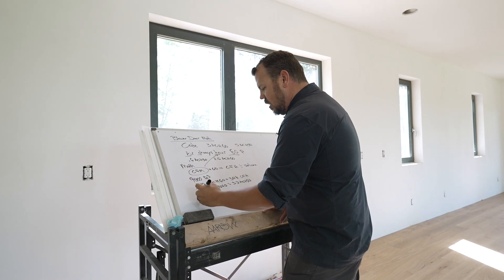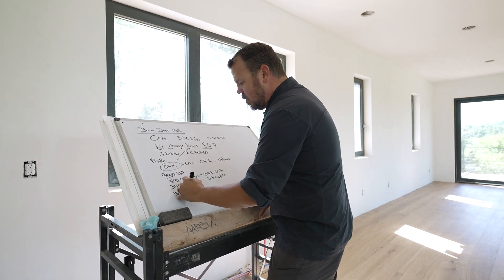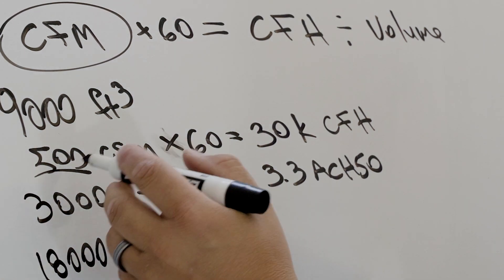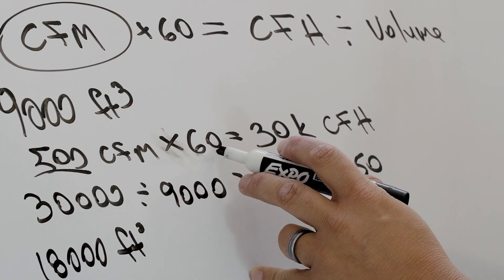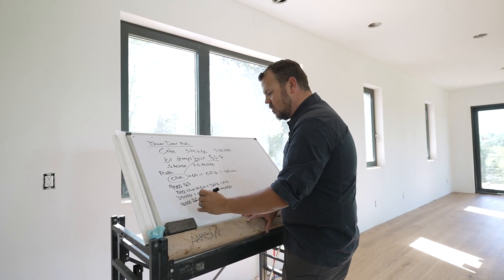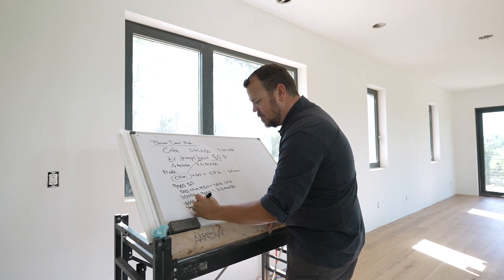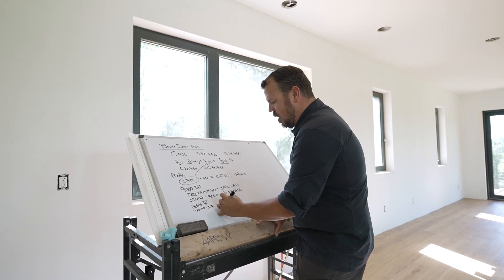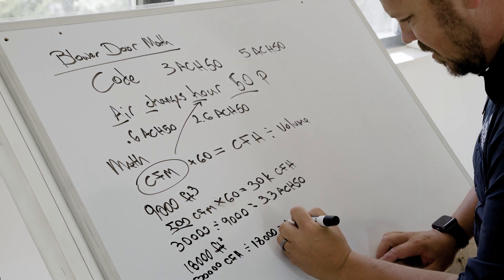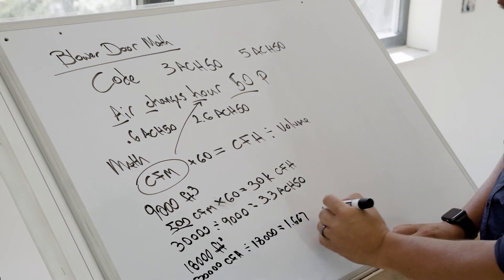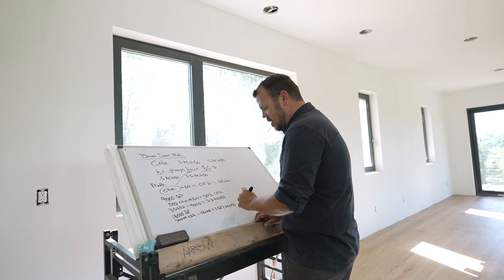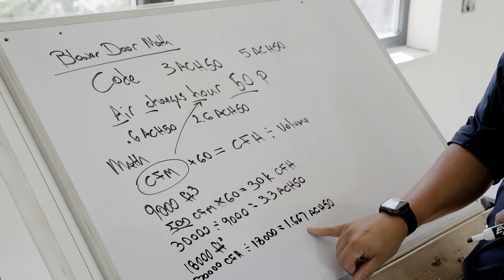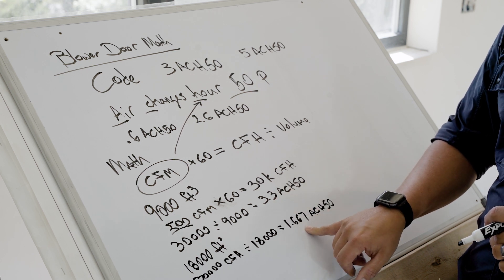Now let's do a 2,000 square foot house. At 9-foot ceilings that gives us 18,000 cubic feet of volume. Using the same 500 CFM of leakage times 60 gives 30,000 cubic feet per hour. Dividing 30,000 by 18,000 gives us approximately 1.67 ACH50. By keeping air leakage the same but doubling the house size, we basically cut the ACH number in half.